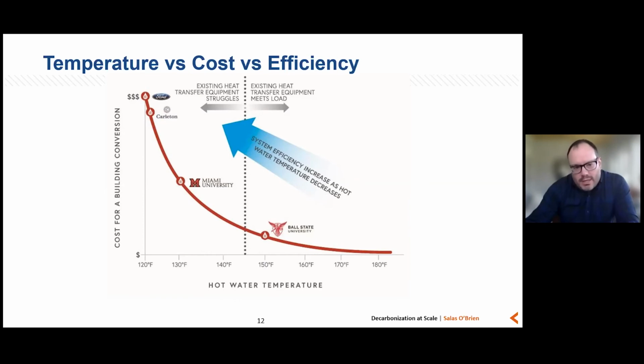That Ford project I mentioned is all the way down to the 120 degree end of the spectrum. And that really is a really important balance to carefully consider: how much money will be required to be deployed to change terminal units, air handling pieces, and lots of mechanical components throughout the building stock if you're going to really press the issue on how low you can put that hot water temperature. But of course, the lower it goes, the better you can use an air source heat pump, and the more efficient any heat pump strategy will be to meet that demand.